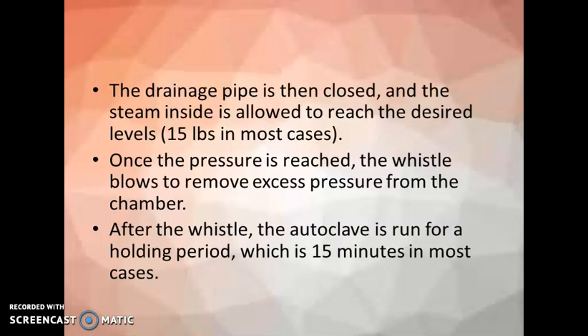The drainage pipe is then closed and the steam inside starts to reach a desired level. That means 15 lbs in most cases. Once the pressure reaches 15 lbs, the whistle blows to remove excess pressure from the chamber. After the whistle, the autoclave is run for a holding period, which is 15 minutes in most cases. So this is 15 lbs for 15 minutes at a temperature of 121 degrees Celsius. It is the temperature of a normal autoclave.